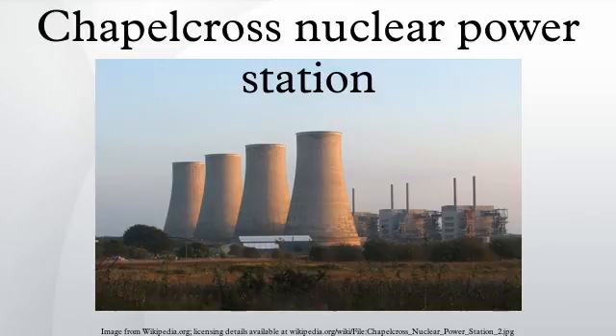Boiler shell defect: cracks associated with brackets in heat exchanger 6 on Reactor 2 were discovered during routine ultrasonic testing. Metallurgical examination of samples of the defect showed that: A, it originated during fabrication in the workshop and prior to an overpressure test of 2.35 times the design pressure; B, there was no evidence of in-service fatigue crack growth; C, the material in which the crack was located was different from that specified in the design.